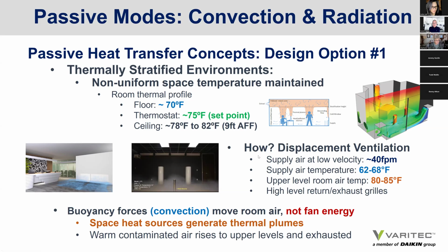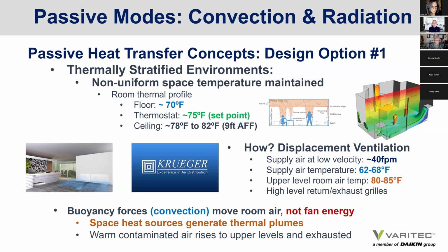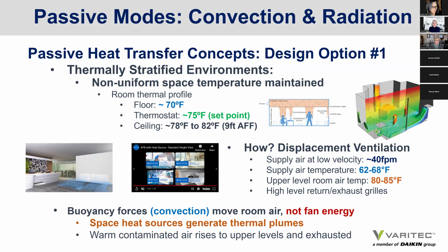If you notice, there's a heating device on the opposite side of the room. Because that device is warmer than the room temperature, it gives off warm air. Warm air rises, cold air falls. And when it does that, it induces the cool air provided by the displacement diffusers into that thermal plume emitted from the heated surface, allowing that warmer contaminated air to rise to the upper levels of a room. So it's a very effective process, and ASHRAE recognizes its effectiveness by assigning it a higher ventilation effectiveness value than conventional HVAC systems.